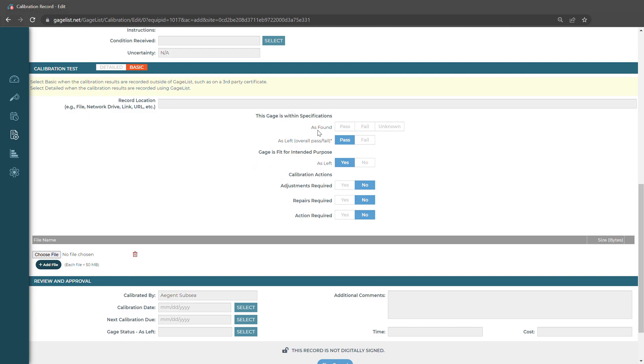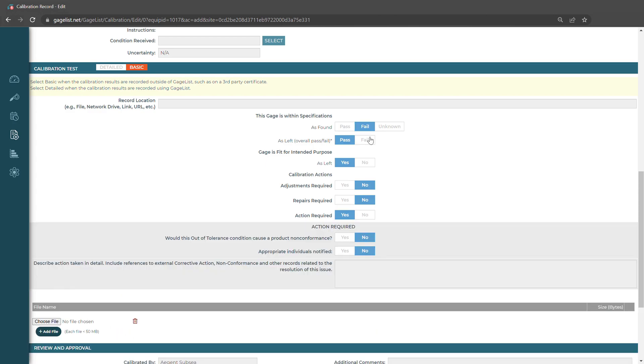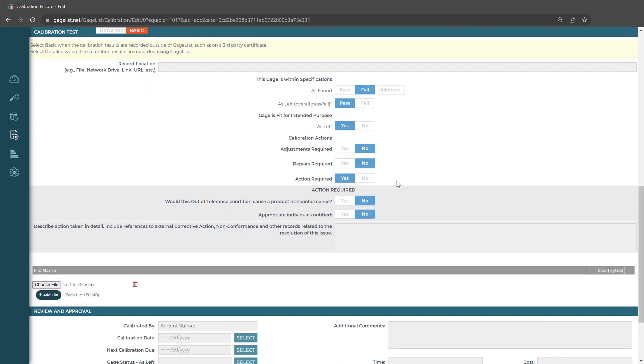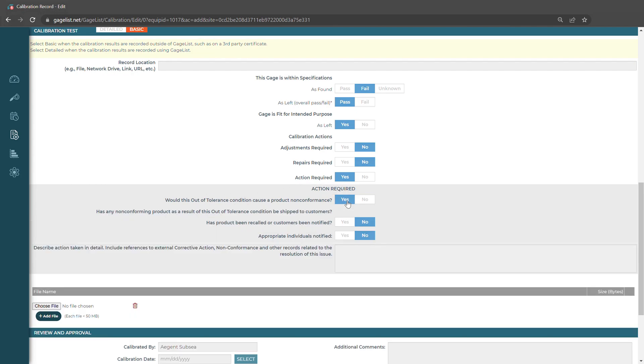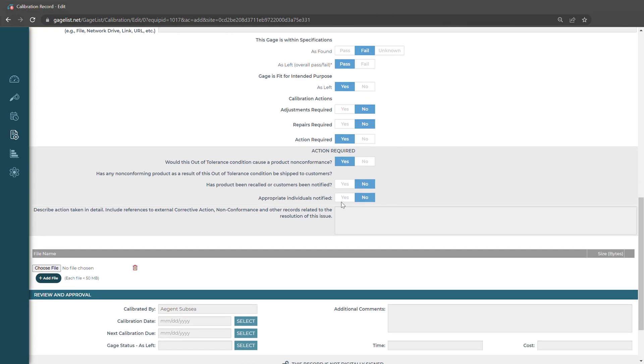It's going to ask us some questions if the gauge was found within specifications and if it overall passed or failed. Depending on what we select, it might trip an Action Required button. Down here where it says Action Required, Yes, it'll ask us if this out of tolerance condition would cause a product nonconformance. And depending on what we select, it'll ask us additional questions and other information to fill out here in the form.